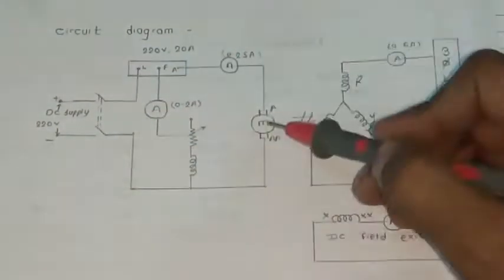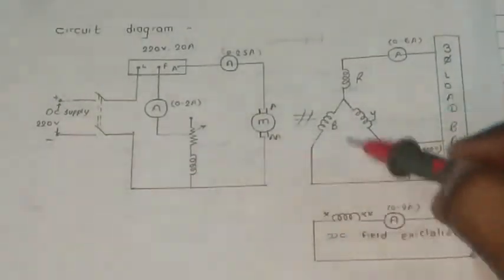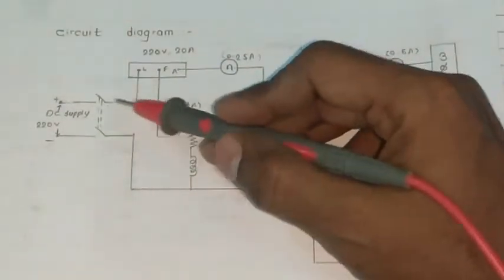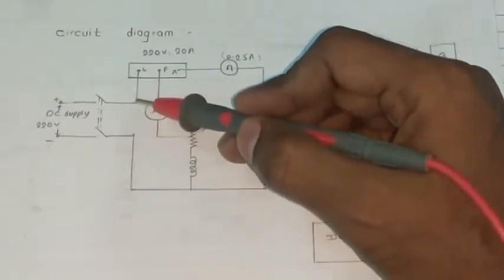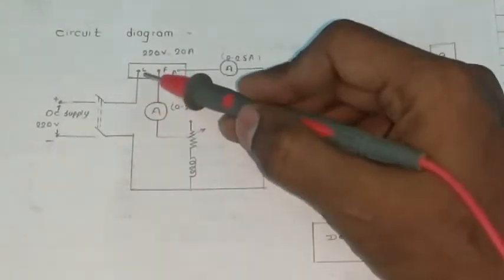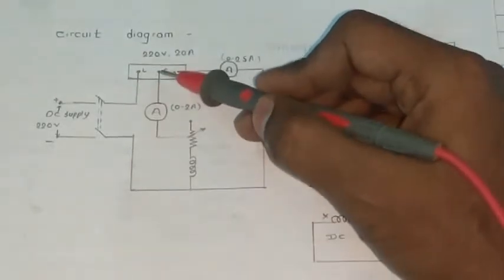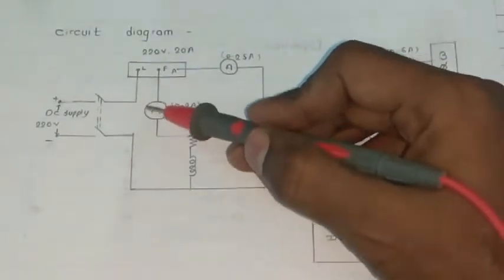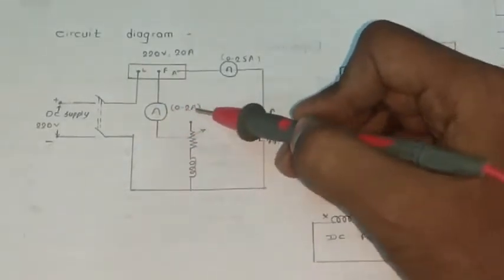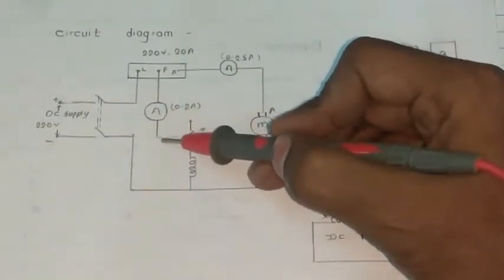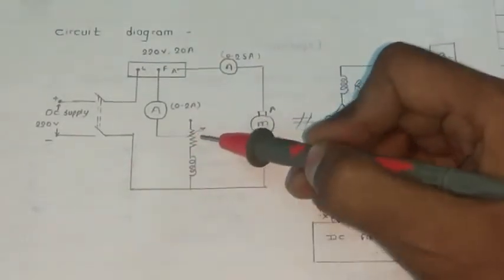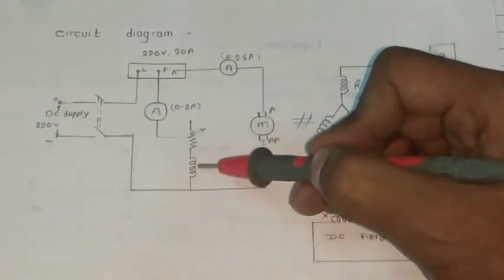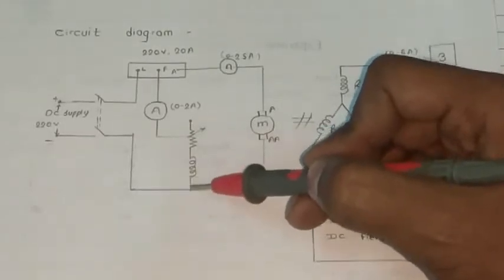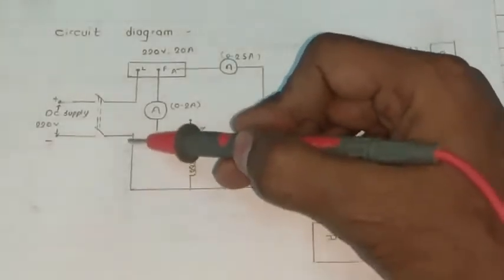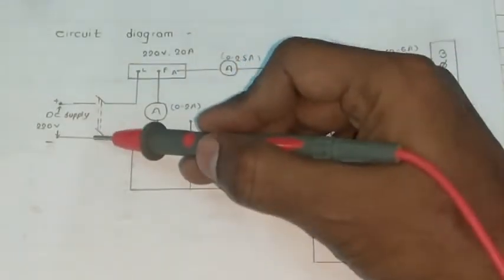You can see the DC supply we are giving to this DC motor of the MG set. The positive DC supply is connected to the 3-point starter L terminal, and from the F terminal we give the supply to the ammeter of 0 to 2 ampere. From the ammeter the supply goes to the rheostat, from the rheostat to the field winding, and from the field winding back to the negative of the DC supply.